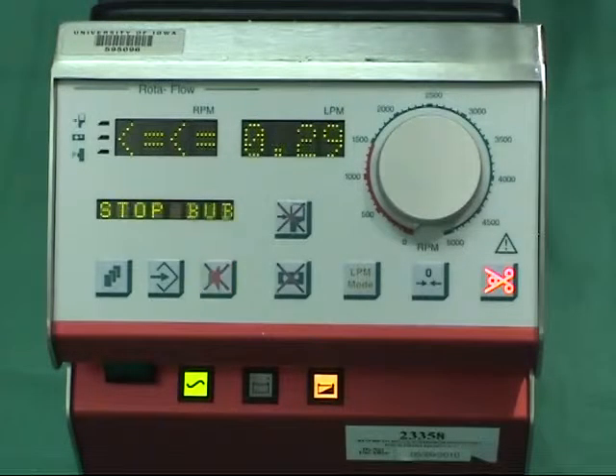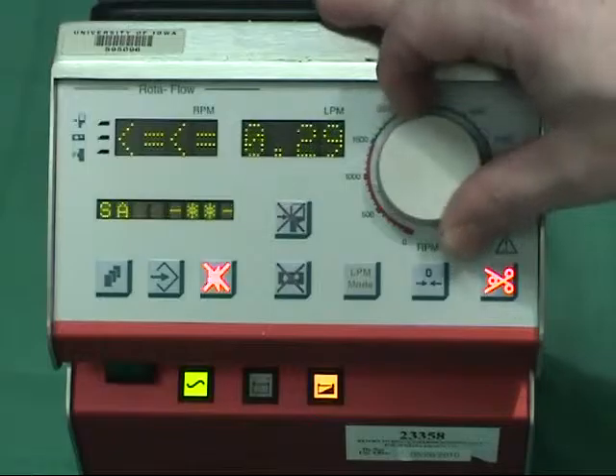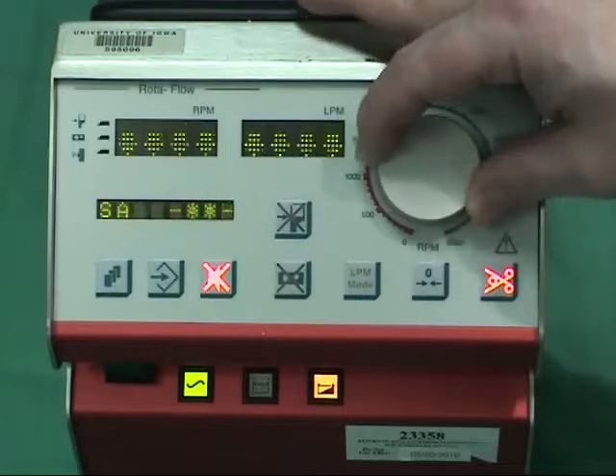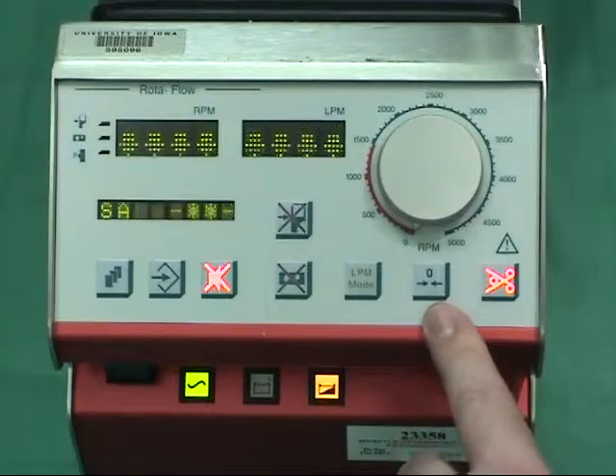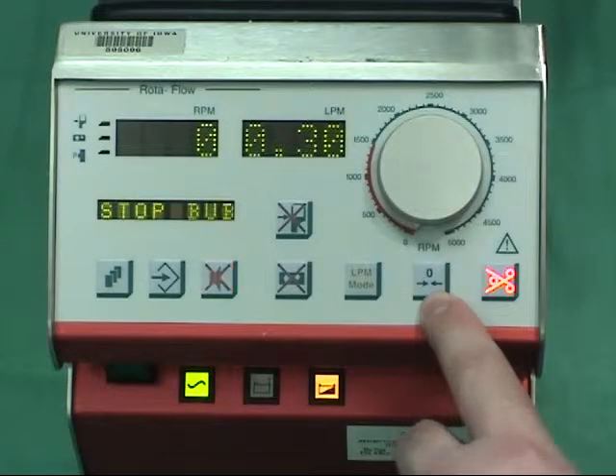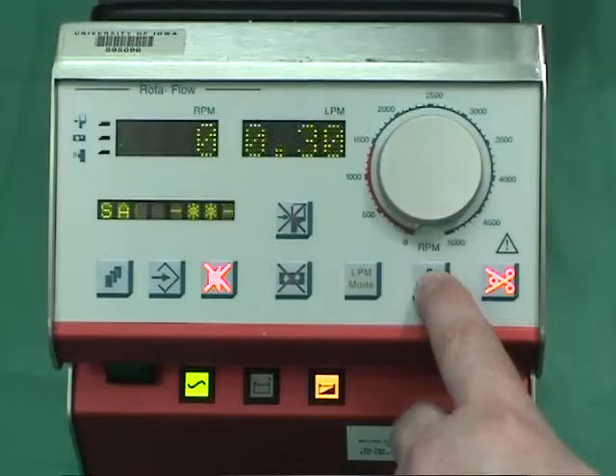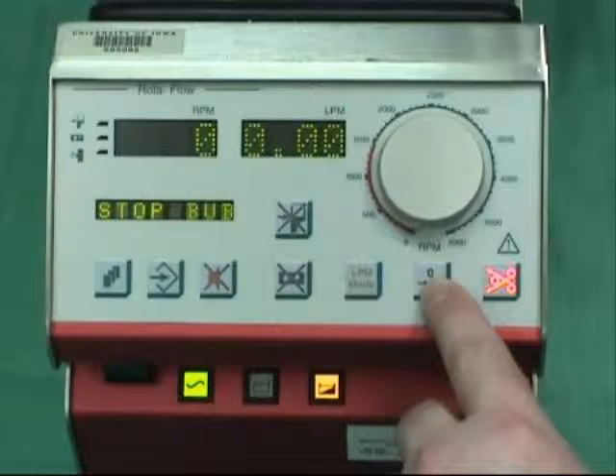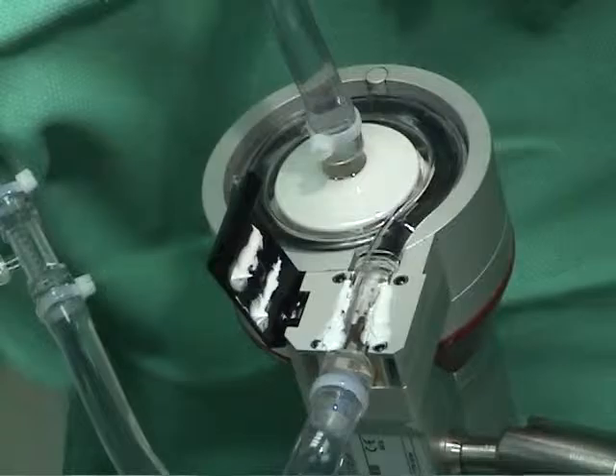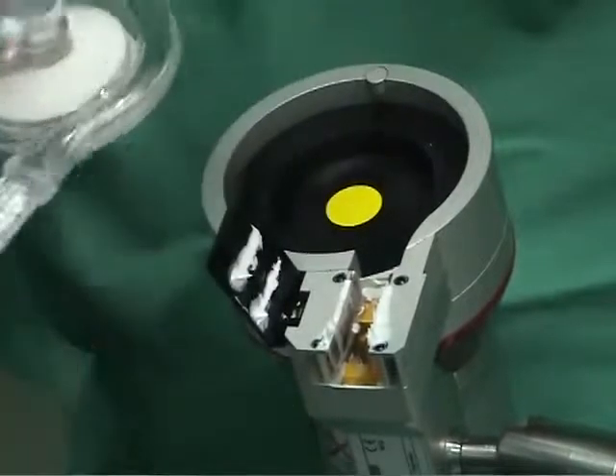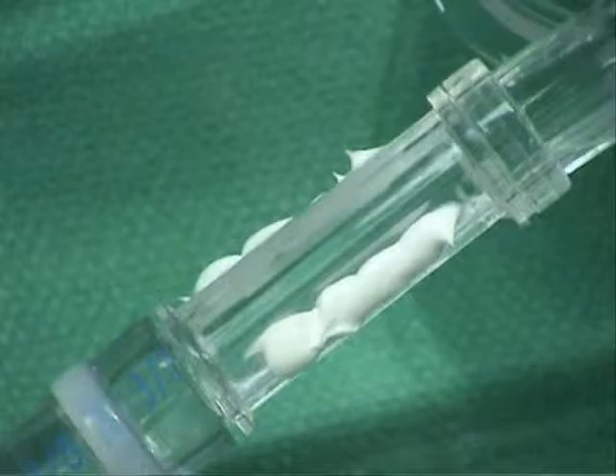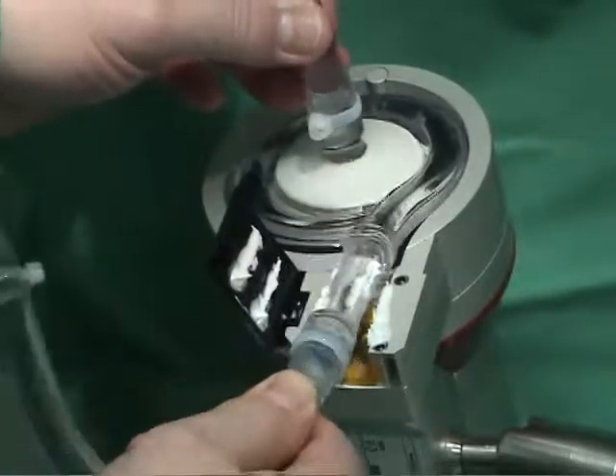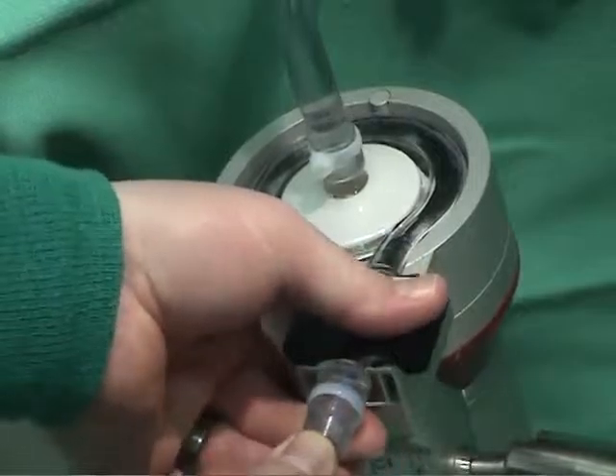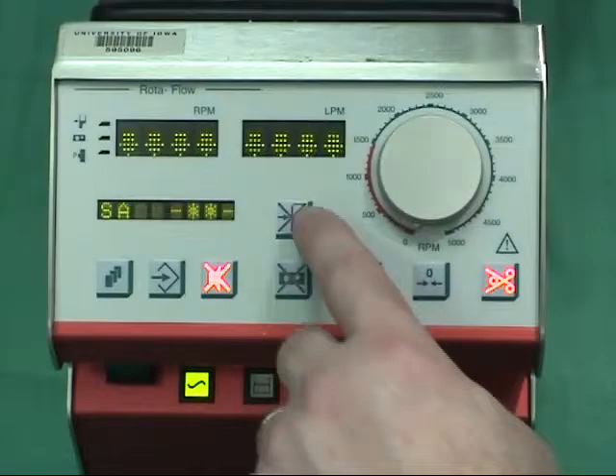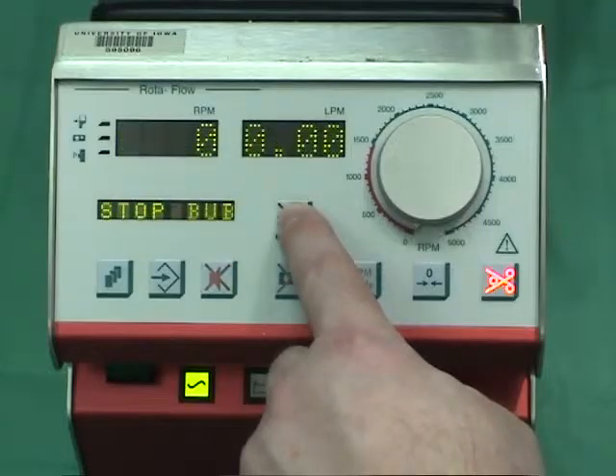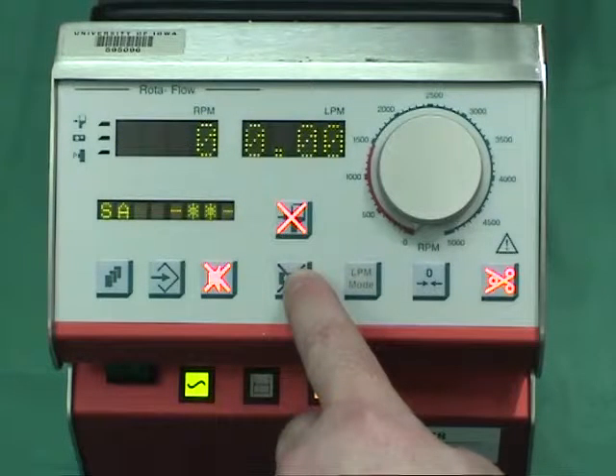Bring the flow adjustment knob to 0. Press the 0 button for 3 seconds until a long beep is heard for 0 calibration. The flow display should now read 0.00. If dashes or SIG are in the LPM display, more paste is needed. Apply paste to the bottom side of the flow probe of the disposable. Re-zeroing is now required. Press both the level override and bubble override buttons for 3 seconds until a long beep is heard.